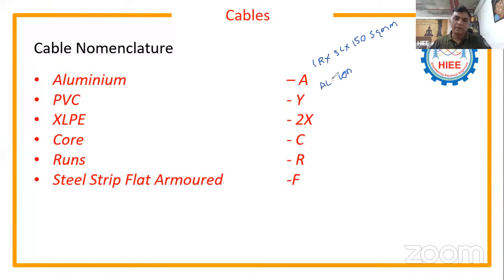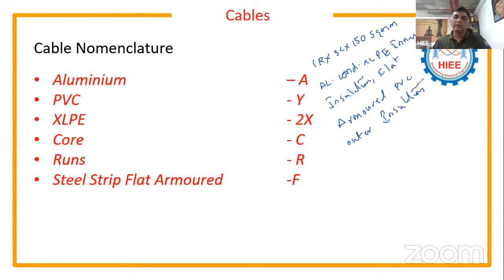Okay, this is aluminum conductor and XLPE inner insulation and flat armored and PVC outer insulation. This is my cable description. For this cable, for example, all this description shall be represented with a nomenclature.